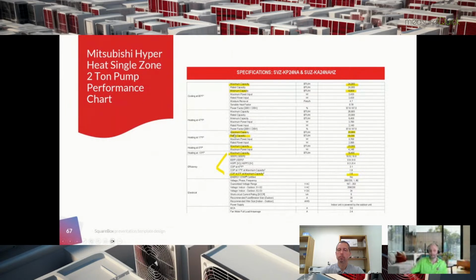You're going to see a lot of times they have maximum capacity and rated capacity. Rated capacity is where you're going to get the rated efficiencies of the system. Maximum capacity is what they can do. When they give you a rated capacity and a maximum capacity, they're telling you, hey, this heat pump can get full capacity, or close to full capacity, at this particular temperature, but at the maximum capacity you're not getting the same efficiency levels. We haven't done the testing to make sure that you're going to maintain these efficiency levels at this maximum capacity. And you see, as we get down here to the lower heating, they're no longer giving you rated capacity because they don't have it.